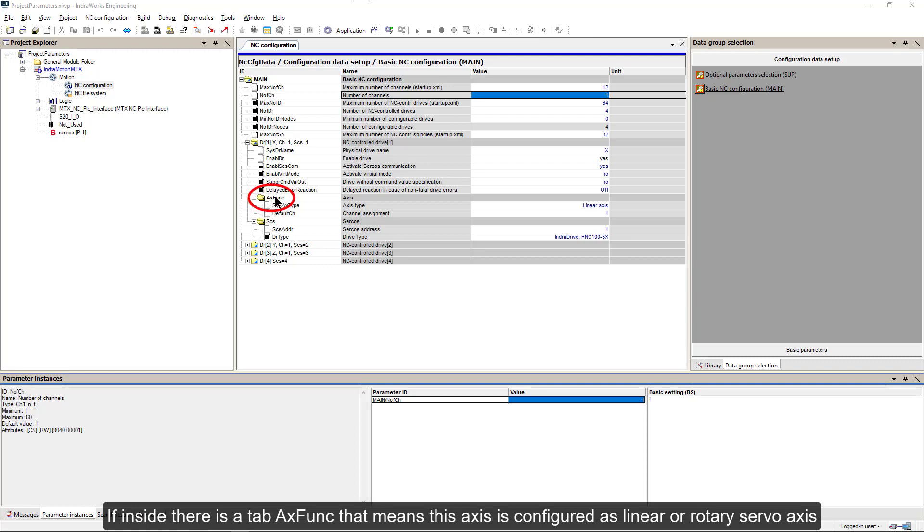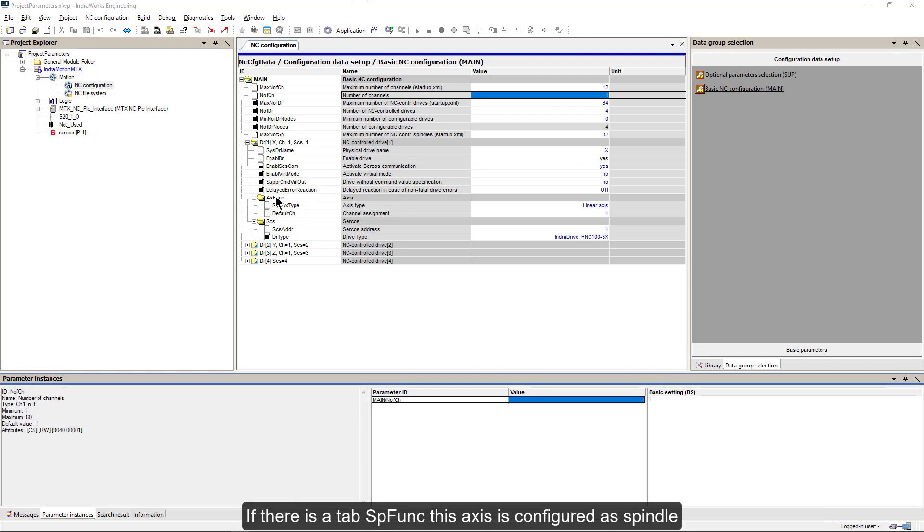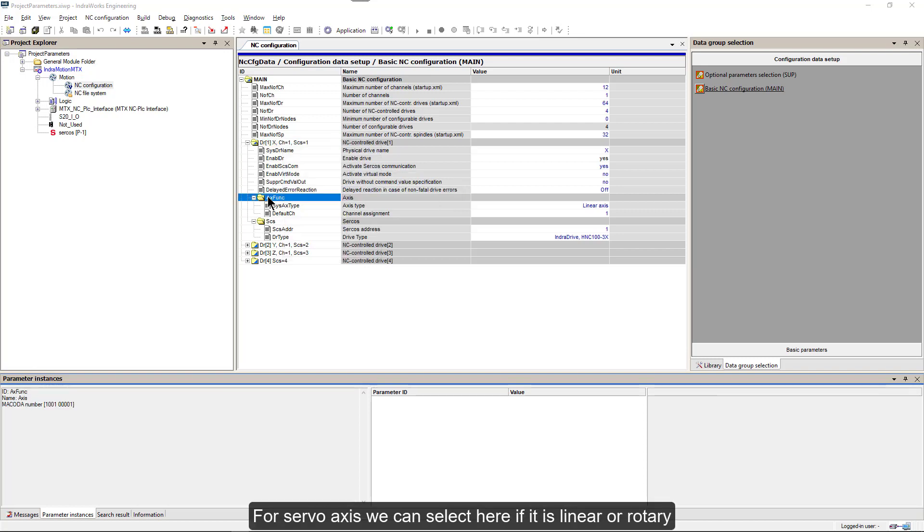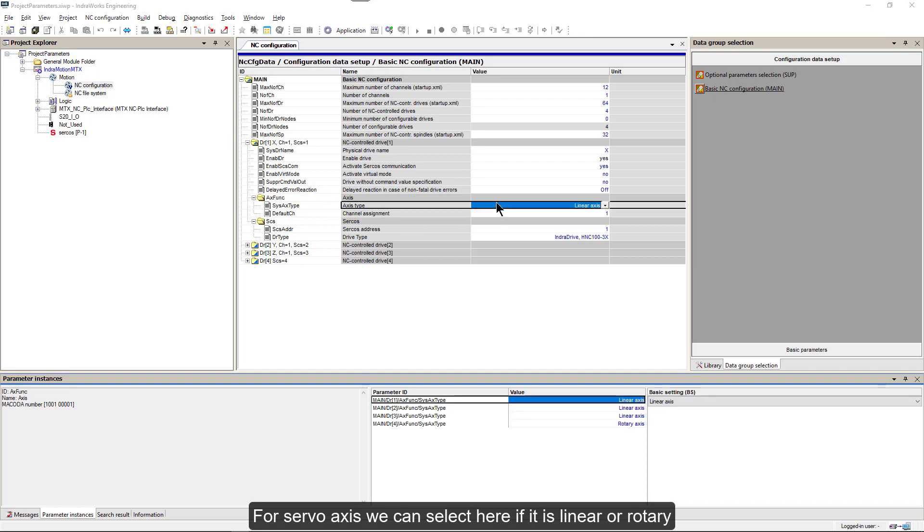If inside there is a tab Axis functionality, that means this axis is configured as linear or rotary servo axis. If there is a tab Spindle functions, this axis is configured as spindle. We can modify Axis type and switch it into Spindle or combination Spindle Axis. For servo axis we can select here if it is linear or rotary.